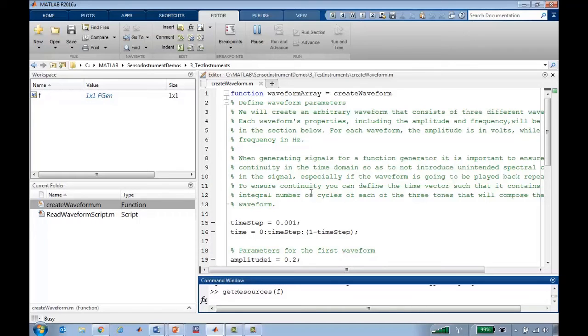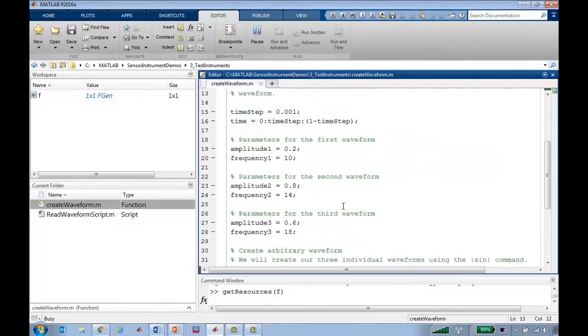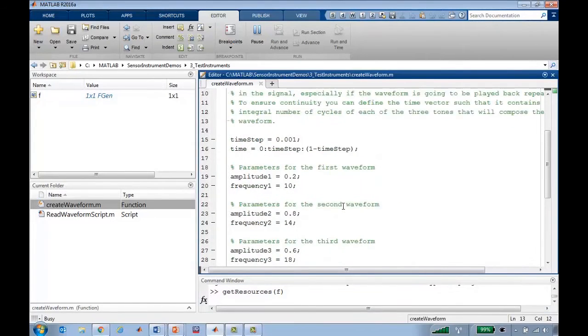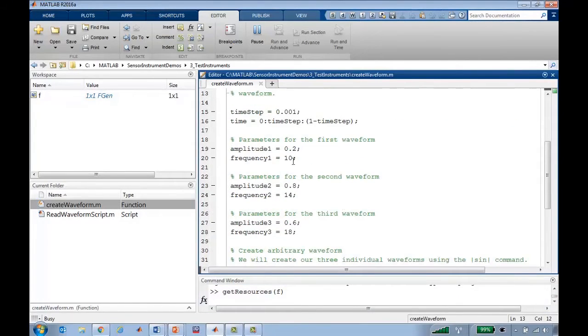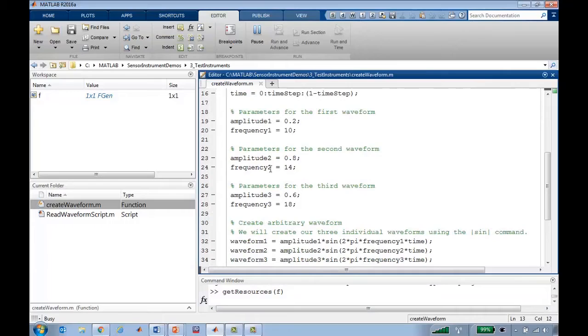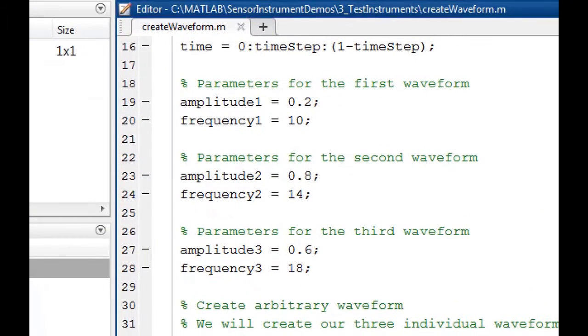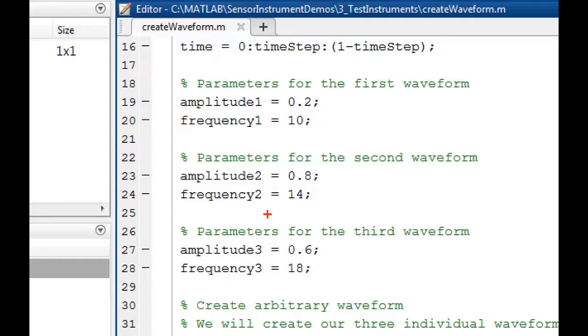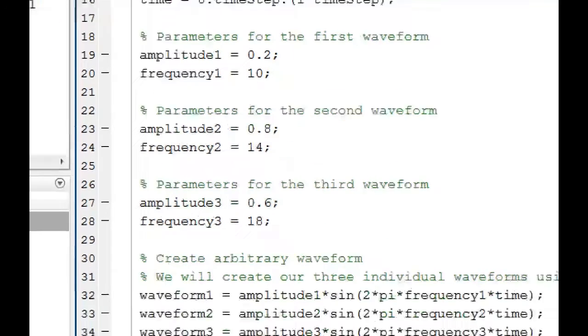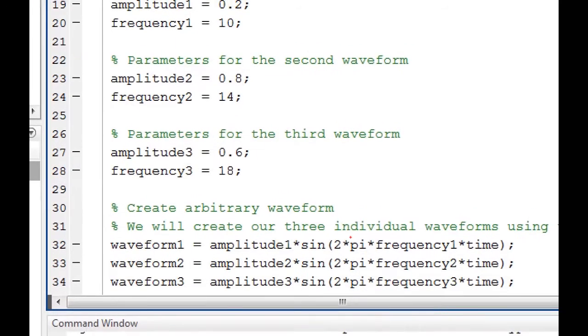Since I'm talking to an arbitrary waveform generator, I'd like to generate an arbitrary waveform and then download it to the device. I begin by defining a waveform composed of three different amplitudes and three different frequencies, and for each amplitude and frequency I generate a sinusoidal waveform.